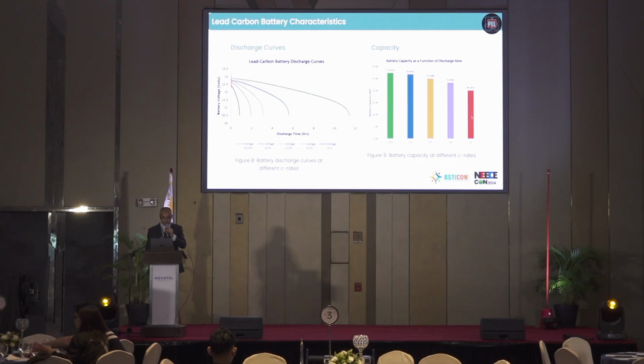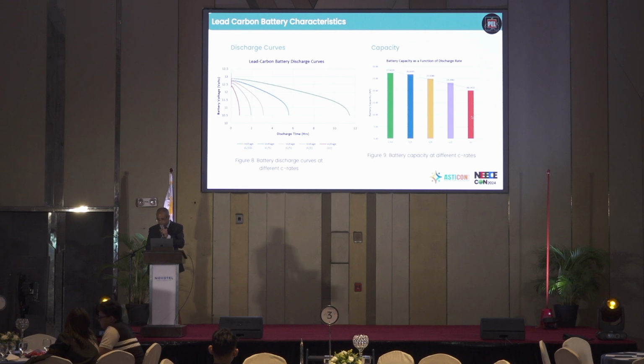It improves the cycle life. It improves the overall discharge and charge characteristics of the battery. These are just some curves from a 24 ampere hour lead carbon battery. If you look at the image on the right, the capacity as a function of discharge rate. Technically, if you compare, I forgot to add the performance of lead acid. For lead carbon, if you look at the capacity here, we discharge the battery at a 10-hour rate all the way to 1 hour. So C over 10 all the way up to 1 C.